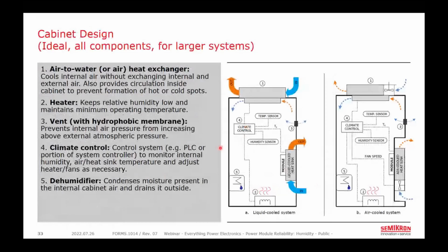And we can show all of these elements working together in a hypothetical liquid or air-cooled cabinet for a larger outdoor system. And larger might be megawatt class solar or energy storage system. Inside and outside air temperature, heat sink temperature, and internal humidity are all fed into a climate control system. And that doesn't have to be really exotic, as there are some commercial standalone controllers available or a simple PLC.